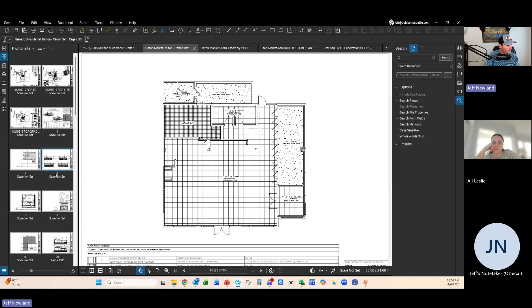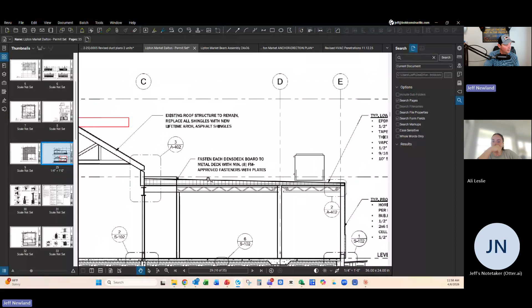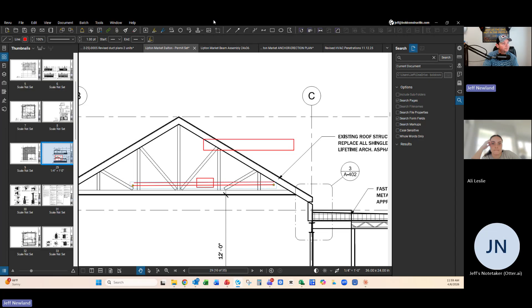If the superintendent lets an electrician get in here first, say we know we've got ductwork running through here, like this example. If that electrician starts running his conduit and it's in the way, somebody's going to be paying a change order, and that's going to be us, because the owner's not going to accept it. They'll say we should have coordinated that better, and they'd be right. We'd have to pay the electrician to move his conduit. That's why handoff meetings and pre-install meetings for each trade are very important, because they help identify who's going where and where they're running their stuff.